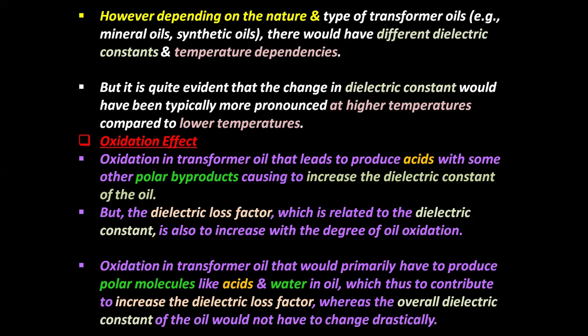Oxidation in transformer oil primarily produces polar molecules like acids and water in the oil, which contribute to an increase in the dielectric loss factor, whereas the overall dielectric constant of the oil does not change drastically.